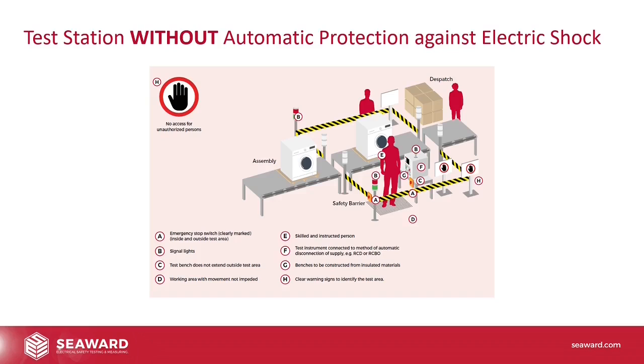In this case, the gentleman there is using a conveyor belt. It would be much easier to have one conveyor belt running through the whole thing, but you cannot do that. You need to have a test bench separate inside. Again, the theory being, if that conveyor belt went live, that colleague in dispatch could get a nasty shock from the end of that conveyor belt if the whole thing was joined together. The equipment is isolated, so you can see that washing machine or tumble dryer there is on a wooden pallet on top of the test bench or test conveyor.